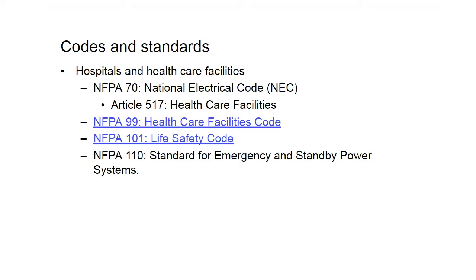Many of the same principles that apply to those types of mission critical facilities also apply to hospitals, albeit through different codes and standards, which we're going to cover here in a second. So the most prominent ones would be the National Electrical Code, obviously, Article 517, which is specific to healthcare facilities, NFPA 99, which is the healthcare facility code itself, NFPA 101, life safety code, and NFPA 110, the standard for emergency and standby power systems.